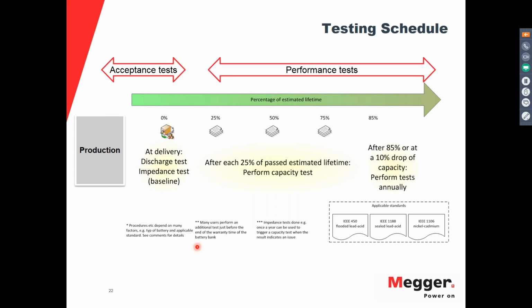Another reason that could be considered destructive is because, if you don't handle the test properly and you don't stop the test when the battery reaches the end voltage, it will affect the battery. But it's not that the test itself is destructive. If you're not careful running the test, you could, of course, damage the battery, but the test itself is not destructive. It's the same with insulation test. If you apply a very high voltage to an insulation that is not rated for that voltage, of course, you're going to break down the insulation. So it's a matter of good practices and good handling of the test and the elements that you use for the test.